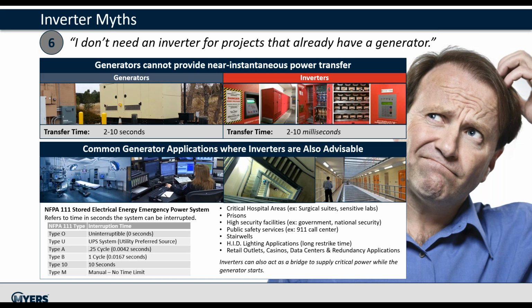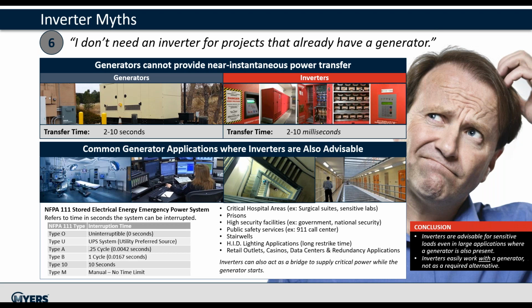NFPA 111 refers to an emergency power system type designation to describe the transfer time, and generators fall in the Type 10 class, while inverters are a Type U class. Critical applications that require Type U were traditionally HID lights, which would have a long restrike time. More recently, applications such as surgical suites, prisons, 911 call centers, and stairwells, which have an outage of seconds that can result in an undesirable effect. So the takeaway from this slide is that inverters can work alongside generators for applications where the long transfer time is a concern or sensitive areas that require redundancy.